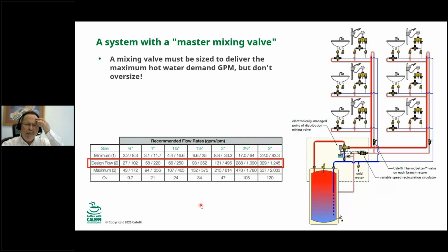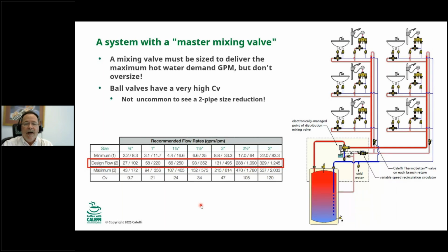Now remember, if you're buying a master mixing valve that has a ball type as opposed to a globe valve, they have very high CVs. So it's not unusual to go down 2 pipe sizes to make a control valve properly sized. Okay, don't ever just put in the pipe size for a control valve, because usually that valve is going to be too big and it will try to control near closed all the time and you won't get consistent temperatures. So pay attention to the CVs.